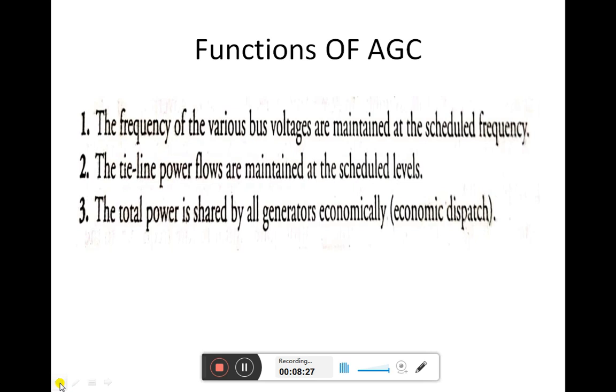If the equilibrium is reached this way, it is in less than 2 seconds. If the mismatch is large, then the governor action has to increase the generation in the units such that equilibrium is reached, when the reduction in the power taken by the load plus the increase in generation makes up for the mismatch. Such equilibrium is reached in 10 to 15 seconds after tripping the unit or connection of additional load.